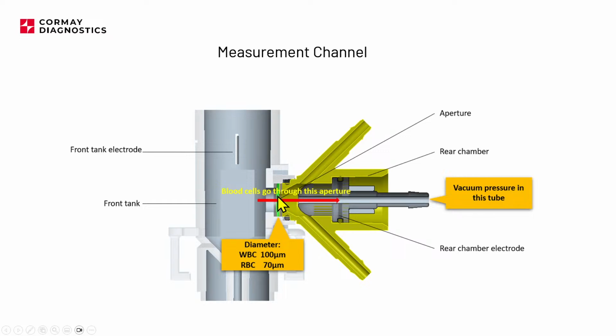Here we have our aperture or counting head. And here we also state the diameter of the aperture. As you can see, the diameter is different for white blood cells and RBC. The reason is that the device is measuring different sizes of particles in each chamber. This size also matters because it was made in such a way to give the analyzer the best possible electrical signal. So the cells dispensed in the diluent pass through the aperture and are drawn by vacuum.